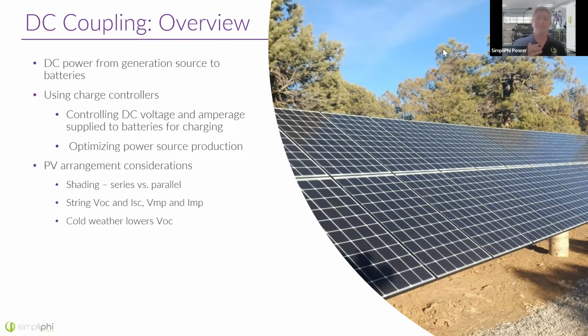One thing to consider with a DC coupled PV array is shading. When you have a string of panels in series and one of them gets shade on it, let's say it's completely shaded, it's producing no power, then guess what? That entire string is producing no power. That series string is dead.